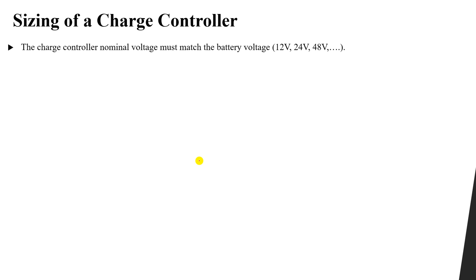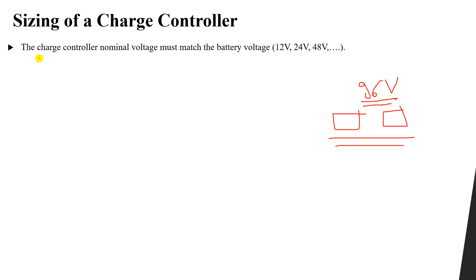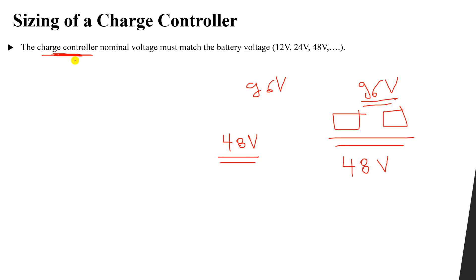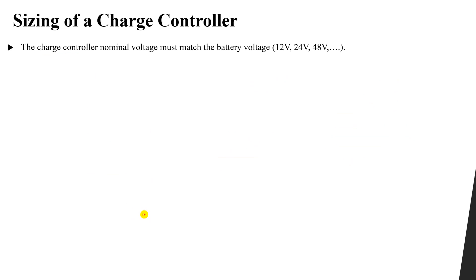Selecting the nominal voltage of the charge controller is really easy — just match the battery voltage with the charge controller voltage. For example, if a group of batteries operates at 96 volts, select a charge controller with a nominal voltage of 96 volts. If the batteries operate at 48 volts, select a charge controller with 48 volts. The charge controller voltage must equal the battery voltage.